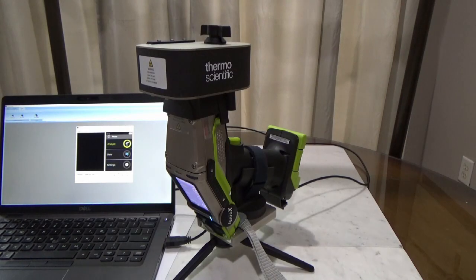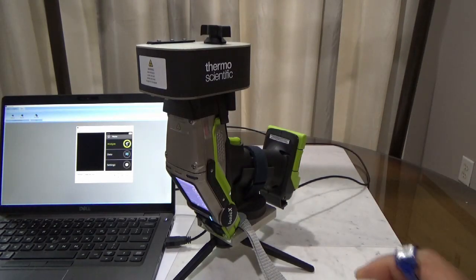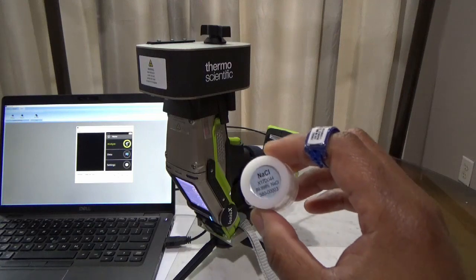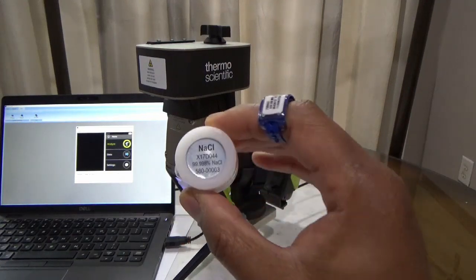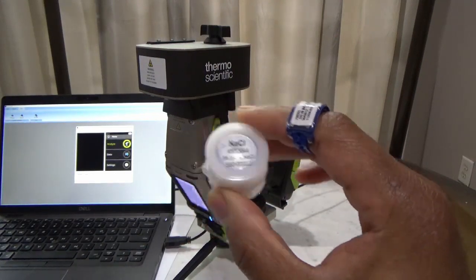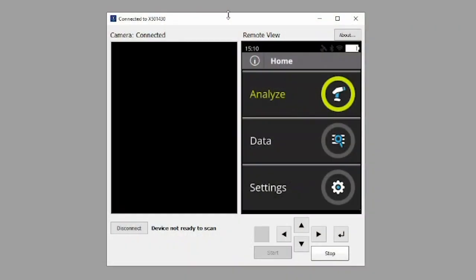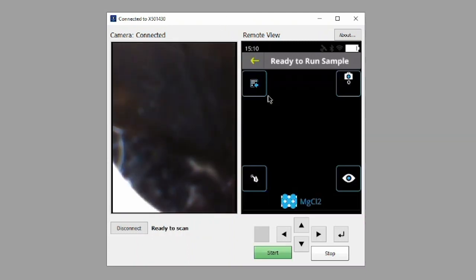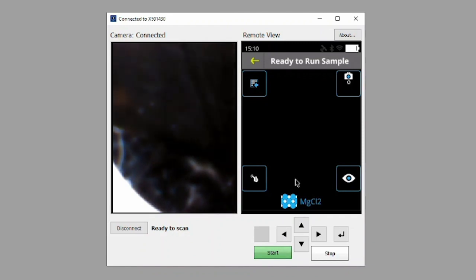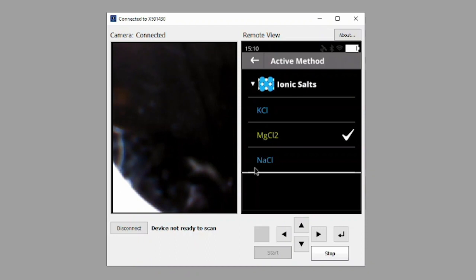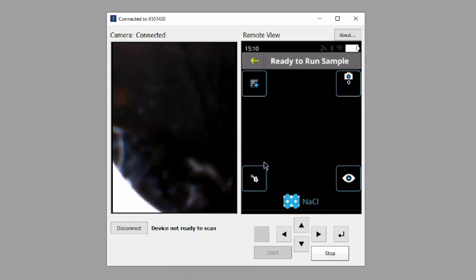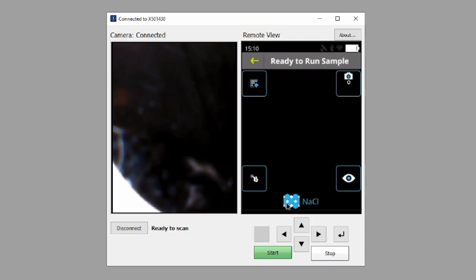Now let's run a sample of a prepared salt material. For this test, I'll use sodium chloride as my sample. Using the Ionic X Remote application, click Analyze to enter the testing screen. First, ensure the correct ID method has been selected for use. Click the icon on the bottom left of the remote view screen and click on the sodium chloride method to select and load that method for use. You can confirm it has been selected by the method name displayed at the bottom of the screen.